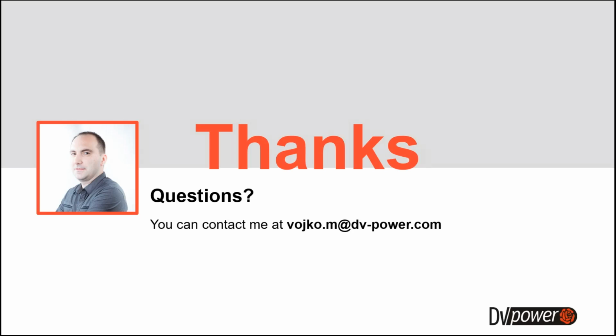One more question that I will answer now because we are running out of time. What are the advantages of resistor OLTC over reactance OLTC? Both resistor and reactive OLTCs have their own advantages and disadvantages. The resistor OLTC is usually used when the tap changer is on the high voltage side, and its advantage is that it can withstand higher voltages. That's why it's placed on the high voltage side. The advantage of the reactive OLTC is that it can withstand much higher currents, and that's why it is used when you have the OLTC on the low voltage side of the transformer. Which is more preferable? That depends.